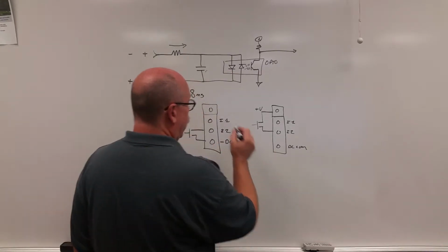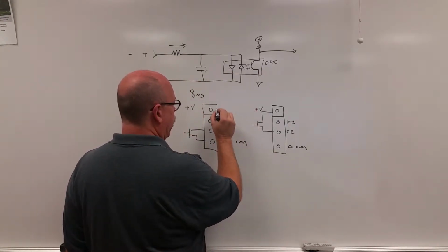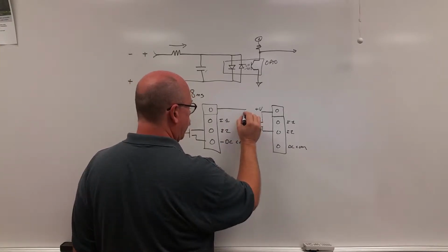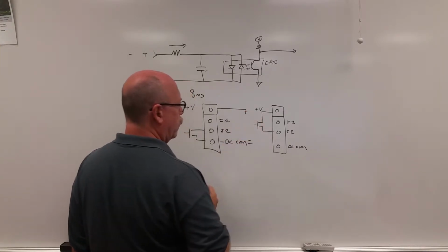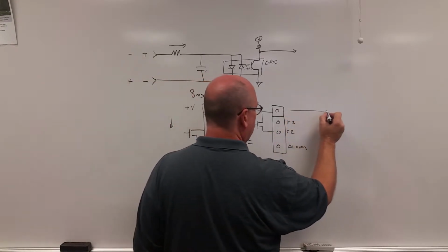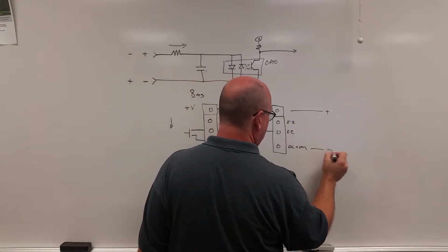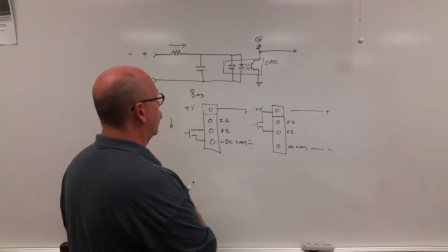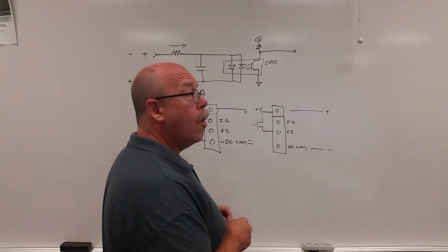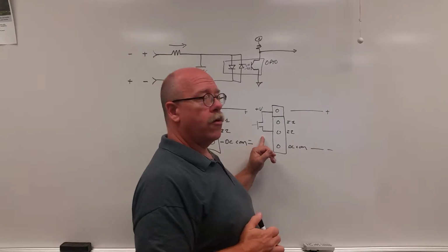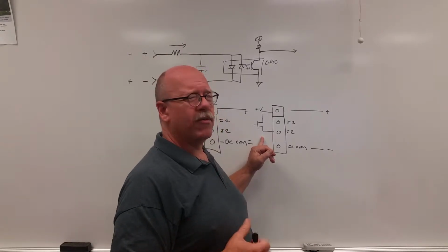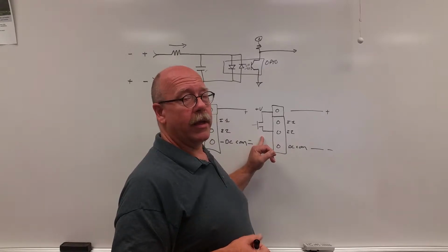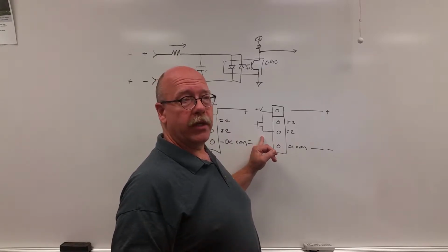In both instances with Allen Bradleys, you have to have an external power supply between these 2 points, typically 24 volts DC. Since a minimum amount of current is required for the input to turn on, this tends to abate the noise that may be present in lines and wires running through machines.